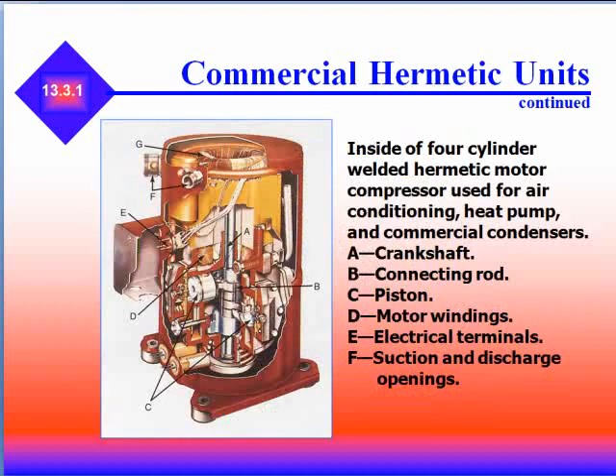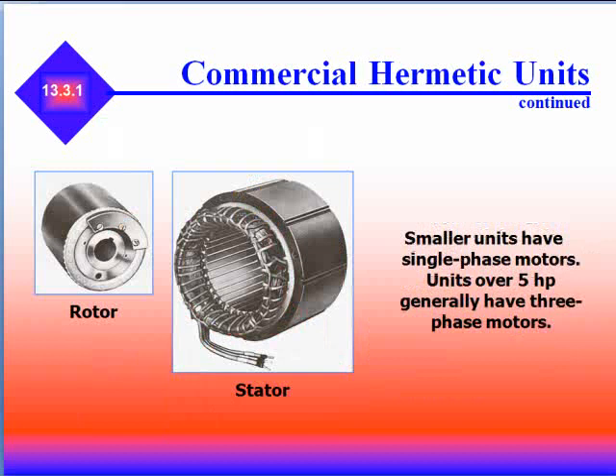The inside of a four-cylinder welded hermetic compressor used for air conditioning, heat pumps, and commercial condensers contains a crankshaft, a connecting rod, a piston, a motor winding, electrical terminals, and suction and discharge openings. Smaller units have single phase; units over five horsepower generally have three-phase motors.